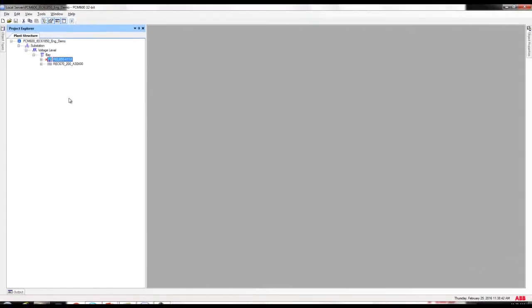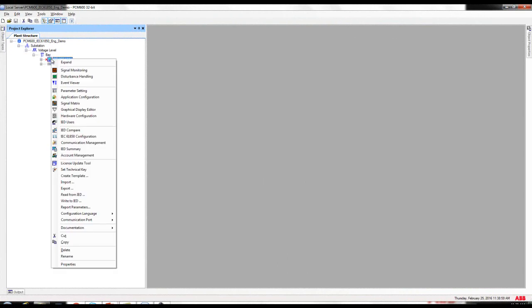With the brief explanation of what we are going to do in PCM600, let's start building the IEC 61850 portion of the relay. Open the IEC 61850 engineering tool, right-click on the relay, and go to IEC 61850 configuration.